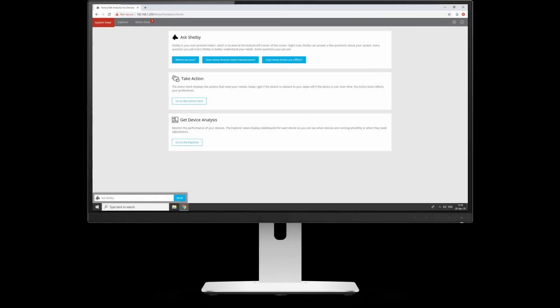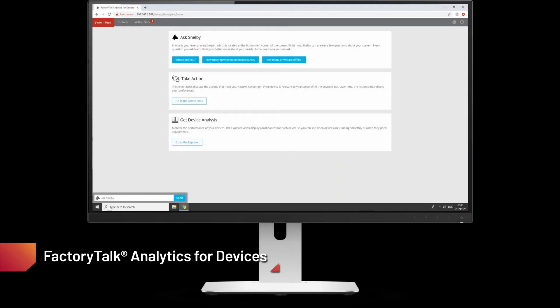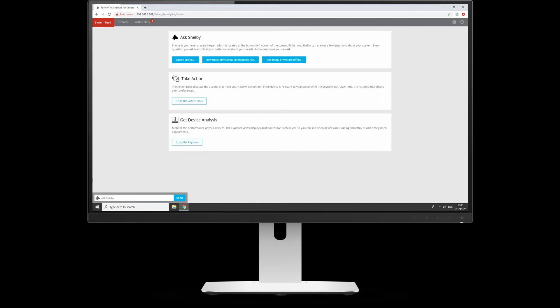Now we're going to take a look at FactoryTalk Analytics for Devices. This is an appliance box that you deploy onto your network. You buy it as a device, plug it into your network, and it will go out and find the first 100 IP addresses on the network. That's from standard. If you need to configure that, you can do things such as whitelisting or blacklisting to get it down to a specific IP address range.